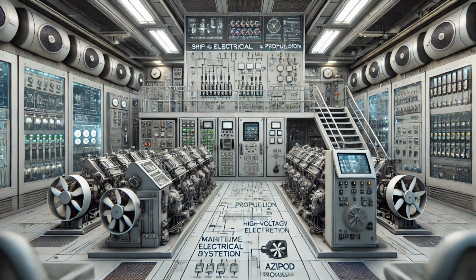It sounds like you really have to respect the power of these systems, even when they're switched off. Exactly. The danger doesn't just disappear when you flip a switch. It's about understanding those hidden dangers and taking the right precautions every time. You need to de-energize the circuits, then verify that they're actually dead, and then properly earth them to bleed off any residual charge. It's not something to be taken lightly.